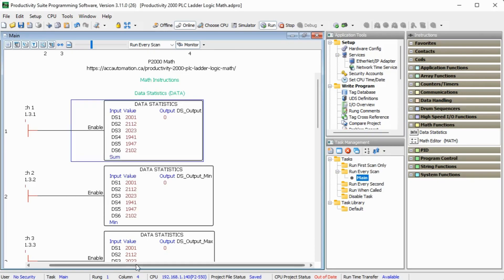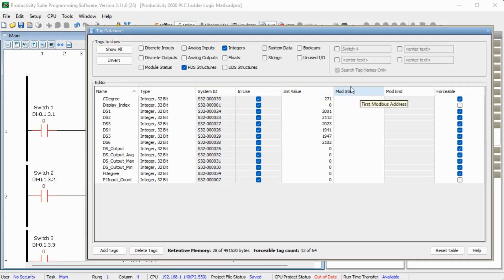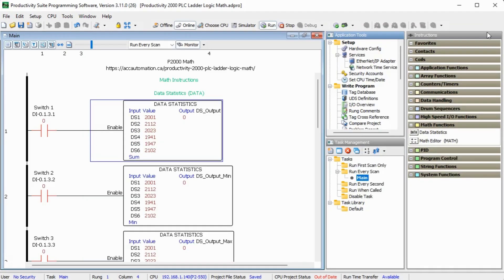We will set ds1 to ds6 as memory retentive tags. Memory is retained after a power interruption or switch from run to program mode. This can be set when prompted by using the memory for the first time or with the tag database. We will assign numbers to our ds1 to ds6 tags.